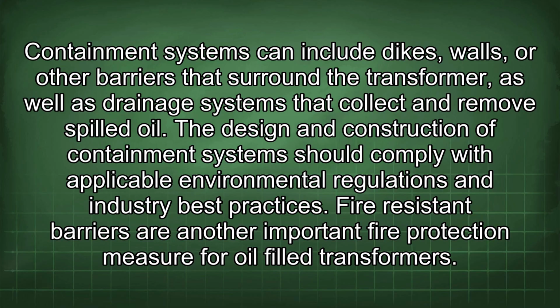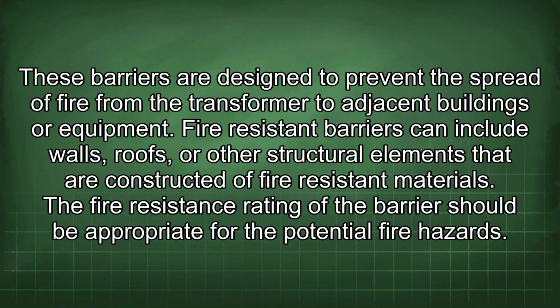Fire-resistant barriers are another important fire protection measure for oil-filled transformers. These barriers are designed to prevent the spread of fire from the transformer to adjacent buildings or equipment. Fire-resistant barriers can include walls, roofs, or other structural elements that are constructed of fire-resistant materials. The fire resistance rating of the barrier should be appropriate for the potential fire hazards.